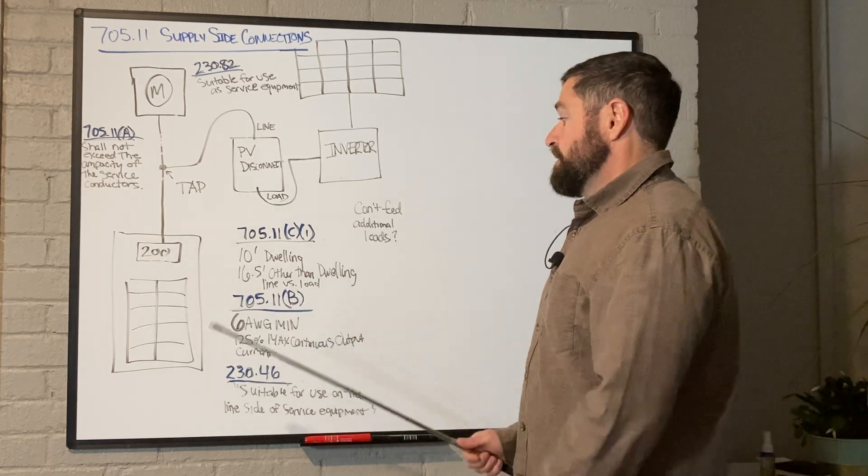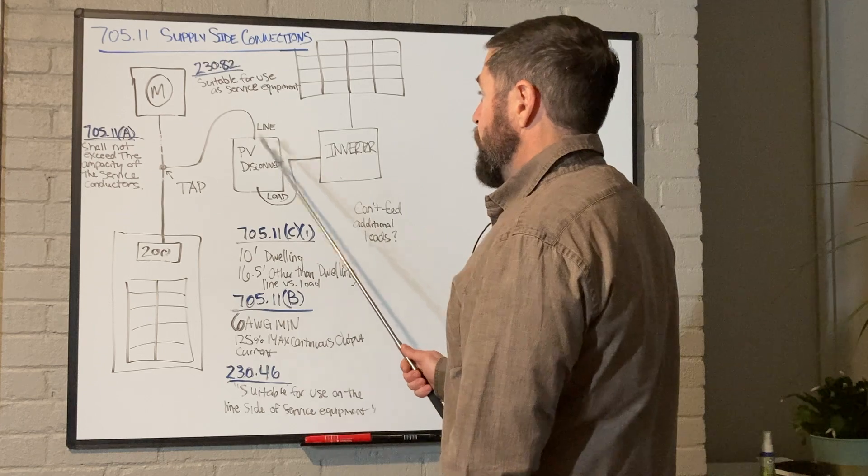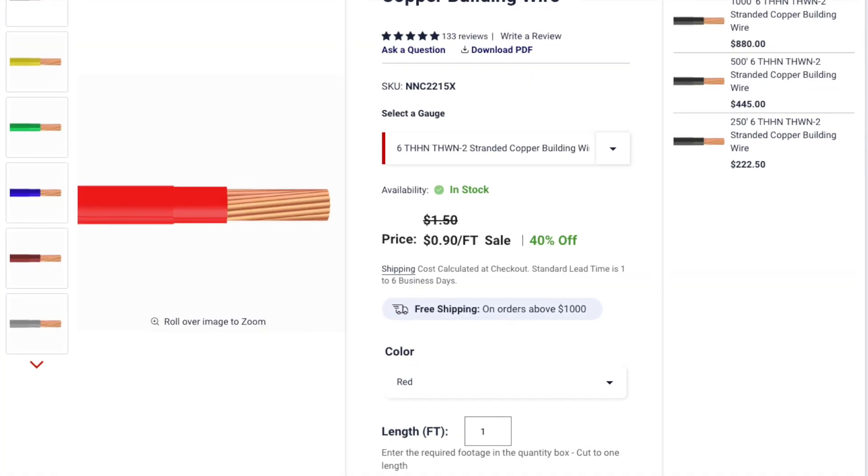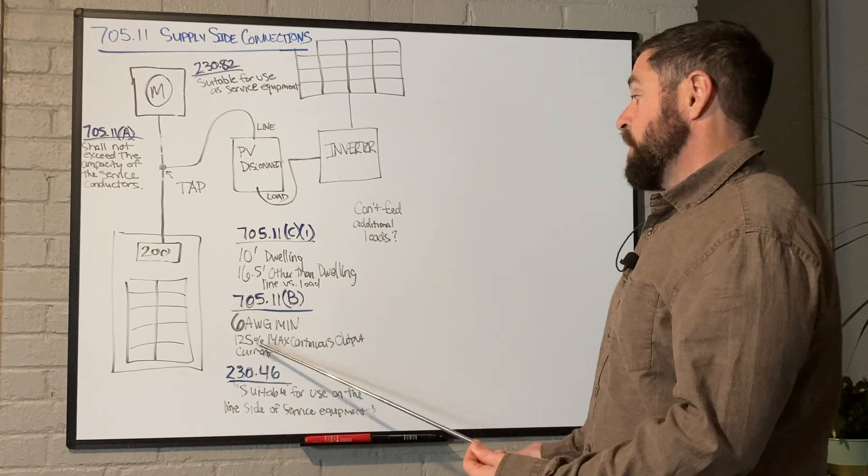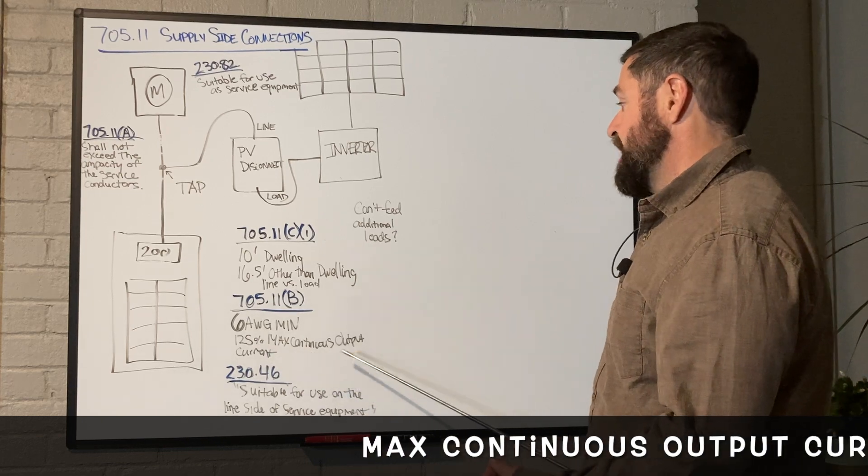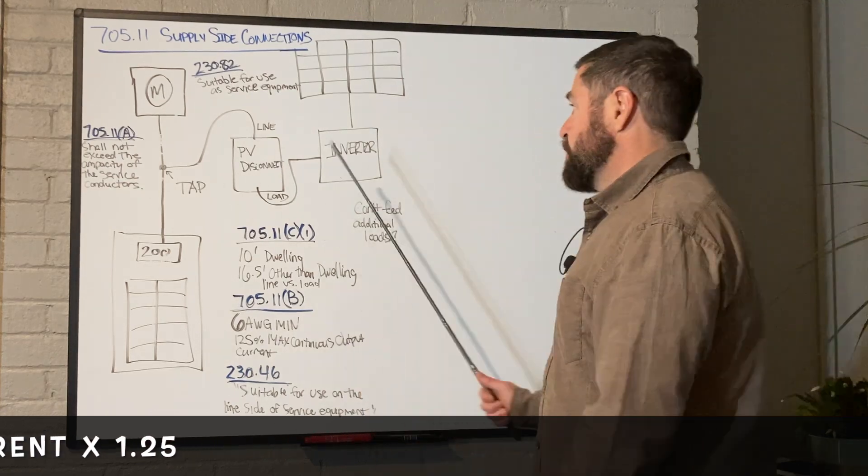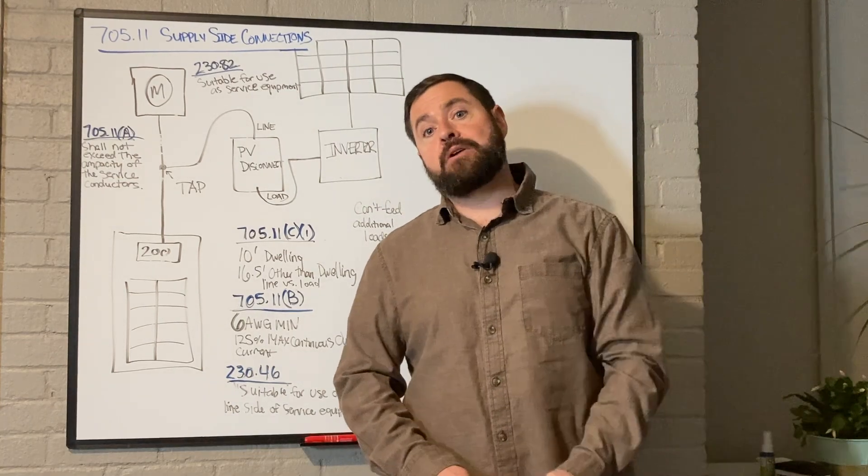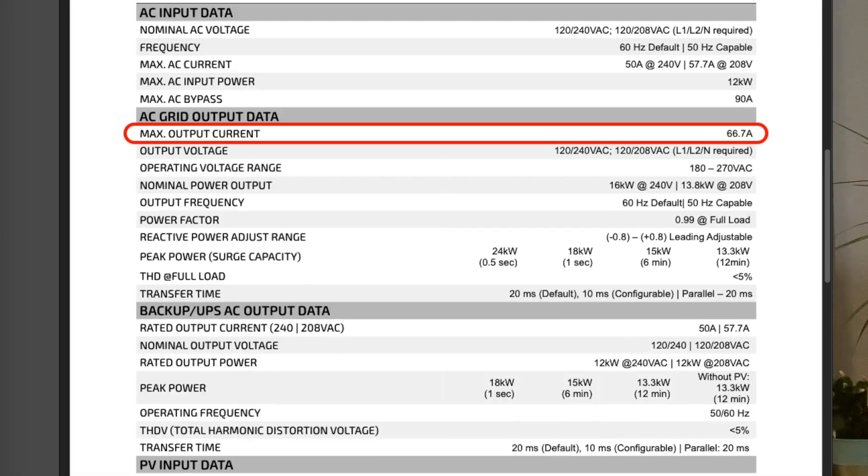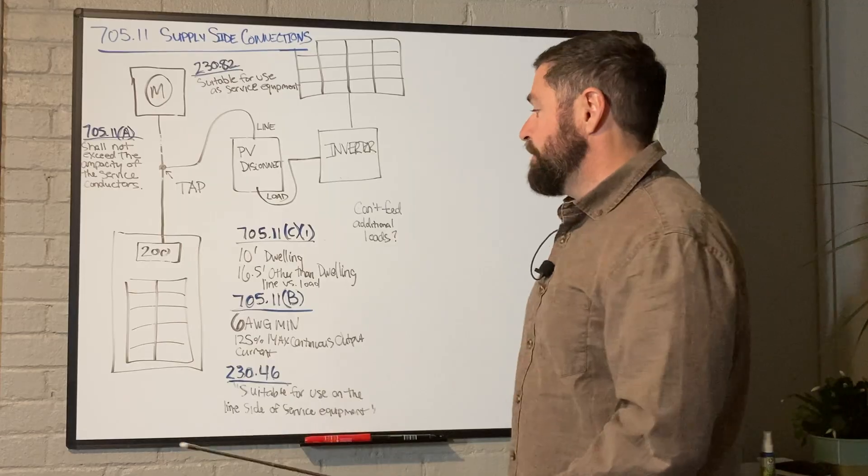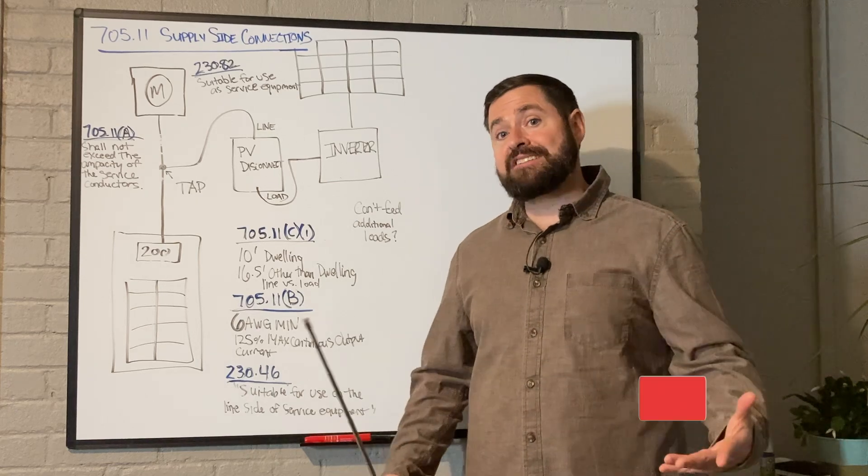Next is 705.11b. This is basically saying that the wire between the tap and your overcurrent protection device has to be a minimum of six gauge and it also has to be at least 125 percent of the max continuous output current of the solar and storage system you're connecting. So essentially, your PV inverter or PV inverters, if you're using micro inverters, they all have a max continuous output current you can normally find that on the nameplate label or on the data sheet. You multiply that times 1.25 to get 125 percent of the max continuous output current of your inverters, and the wires have to be sized at least to that rating.